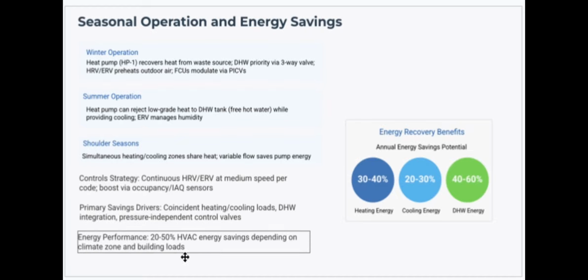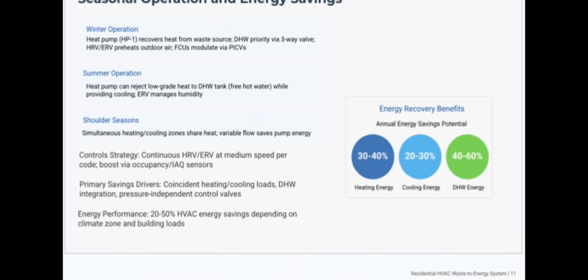Control strategy continuous HRV and ERV at medium speed per code. Boost via occupancy and IAQ sensors. Primary savings drivers: coincident heating and cooling loads, DHW integration, pressure independent control valves. Energy performance, like I said a few times already, is 20 to 50% HVAC energy savings depending on climate zone and building loads. So it may run differently if you have it down south versus up north, or vice versa.